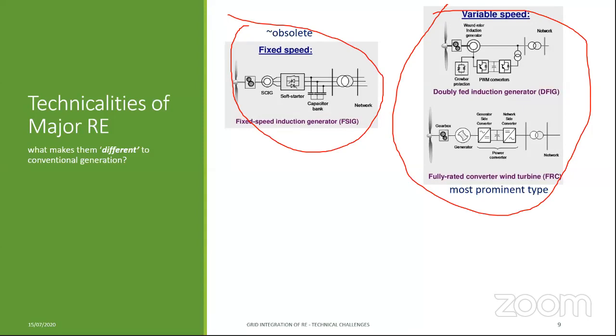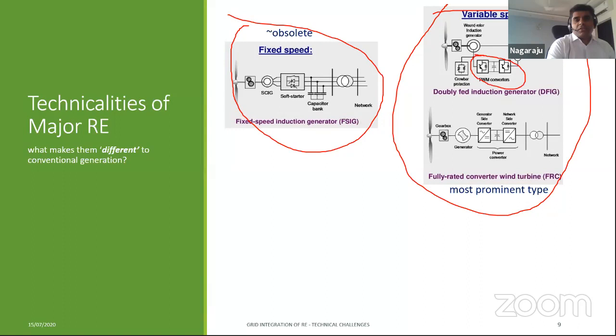All right, okay. So doubly-fed machines are interfaced directly to the grid, but the rotor is kind of decoupled. The rotor excitation is through a converter, which takes the energy again from the grid and feeds it to the rotor. So in a strict sense, the rotor is disconnected from the grid, whereas the stator is actually connected to the grid, and that poses a lot of challenges.